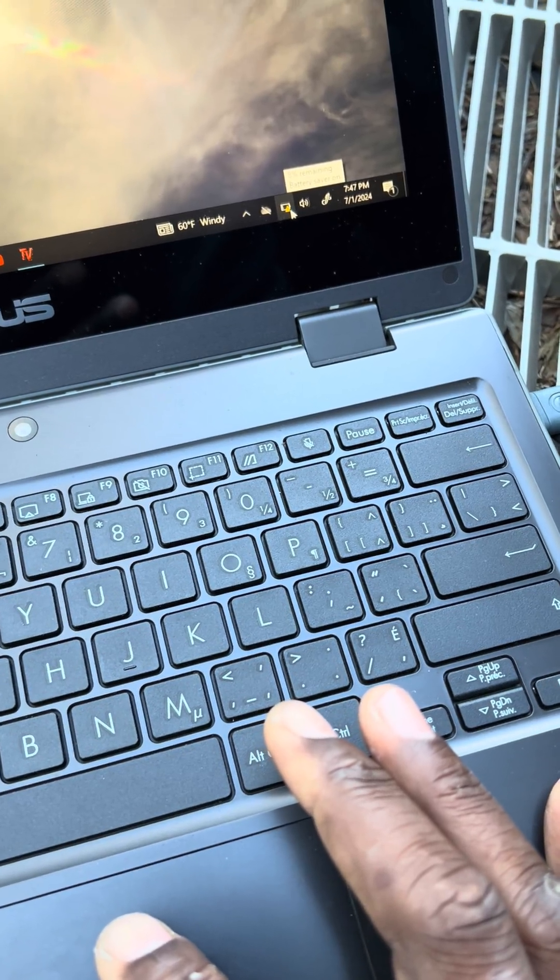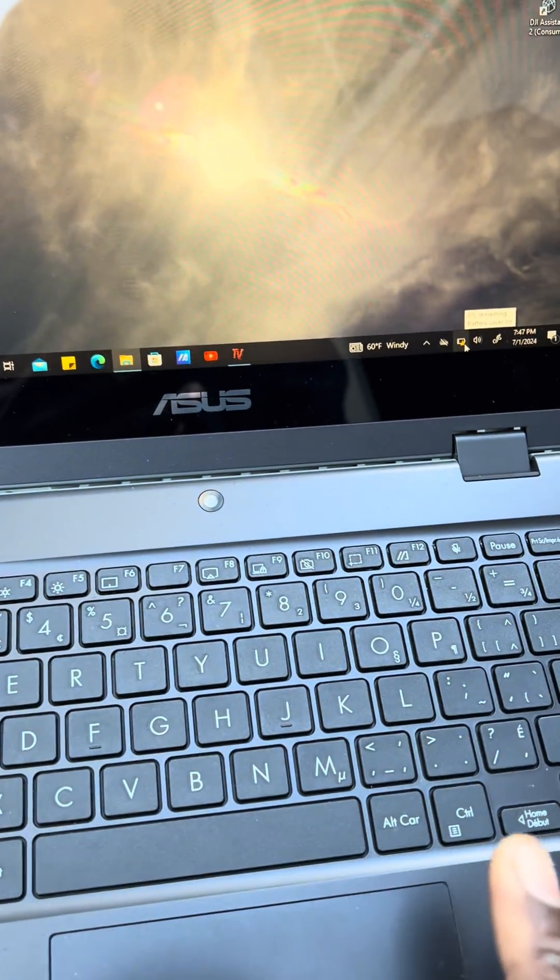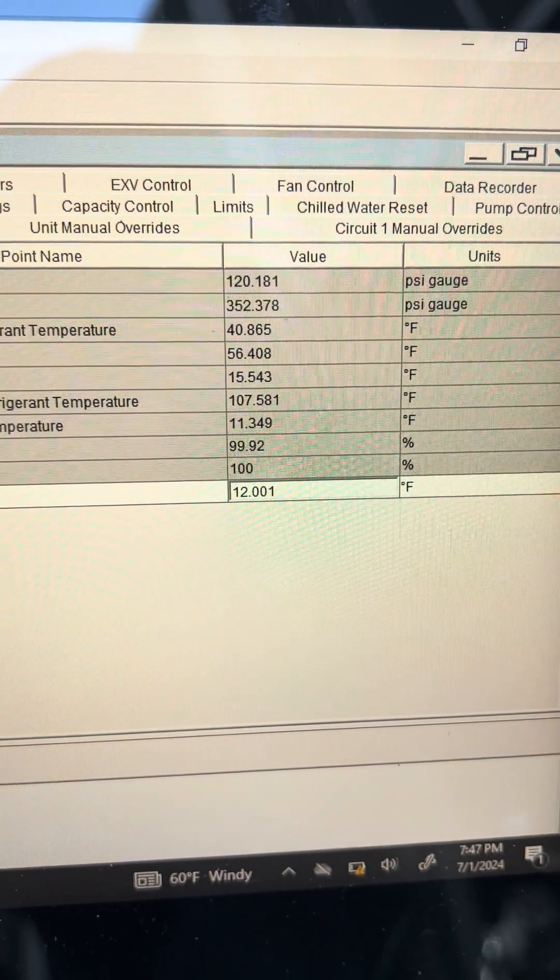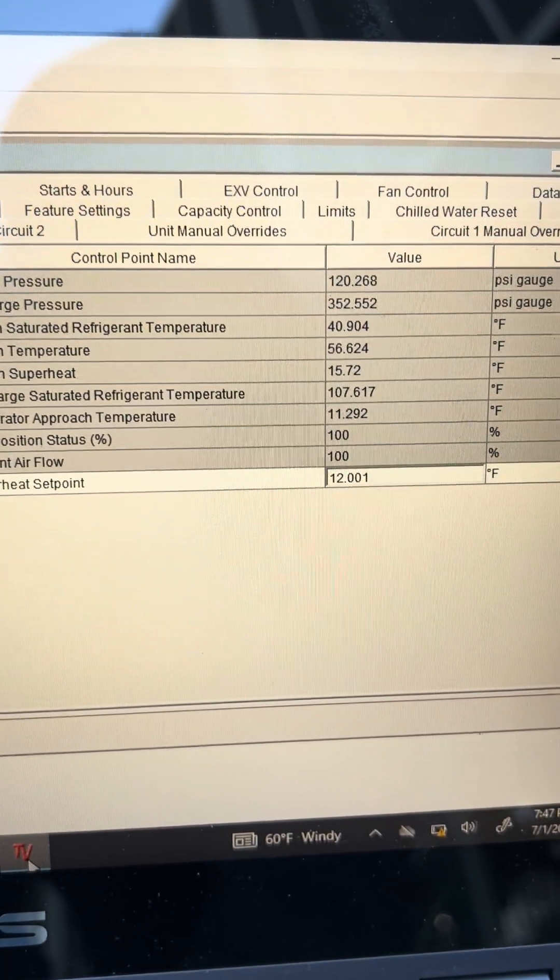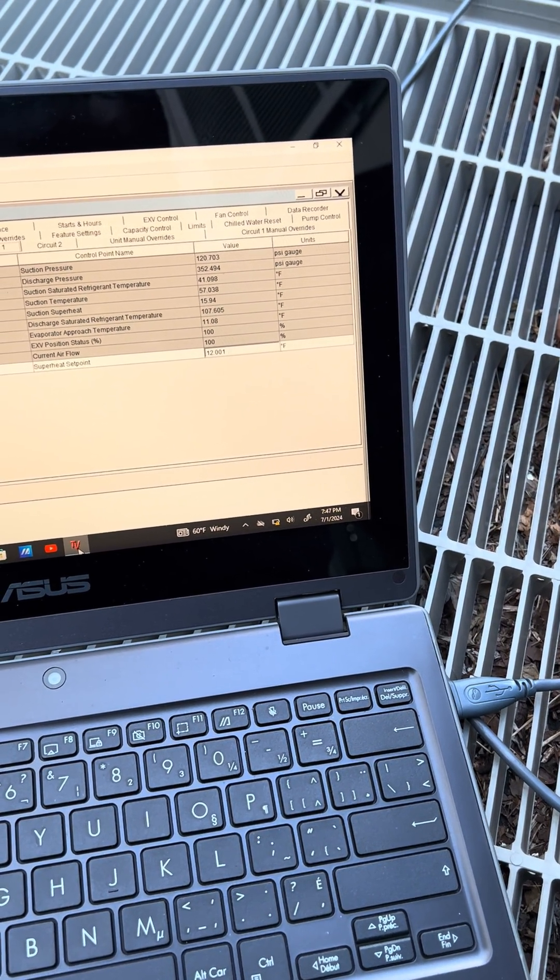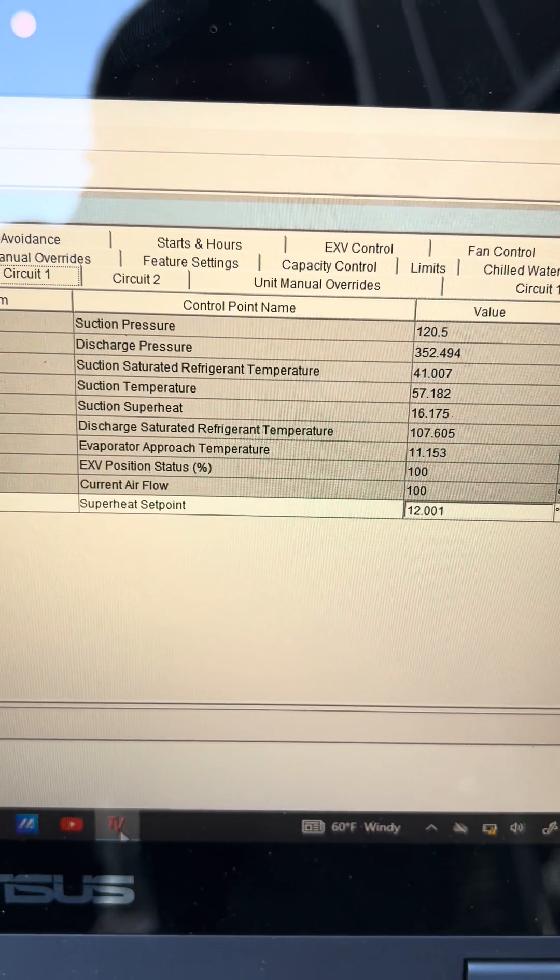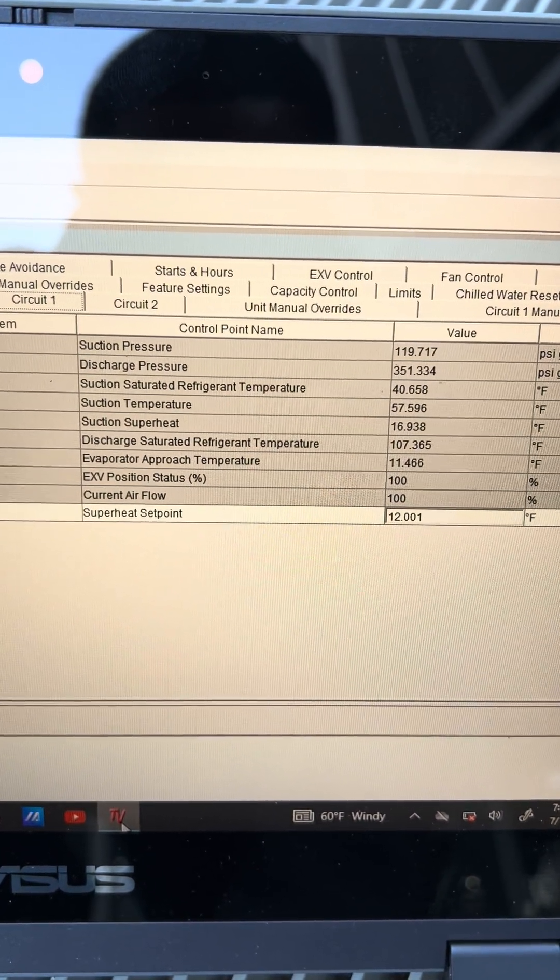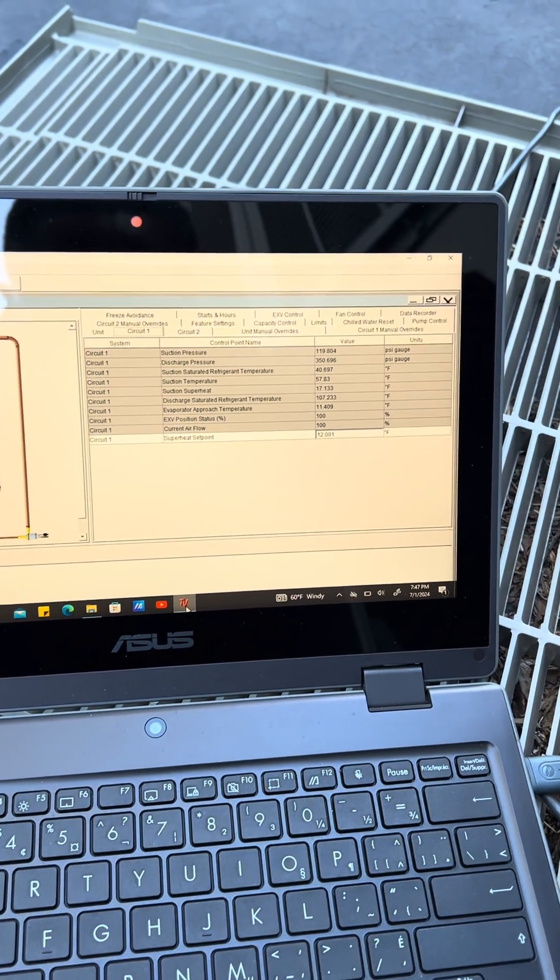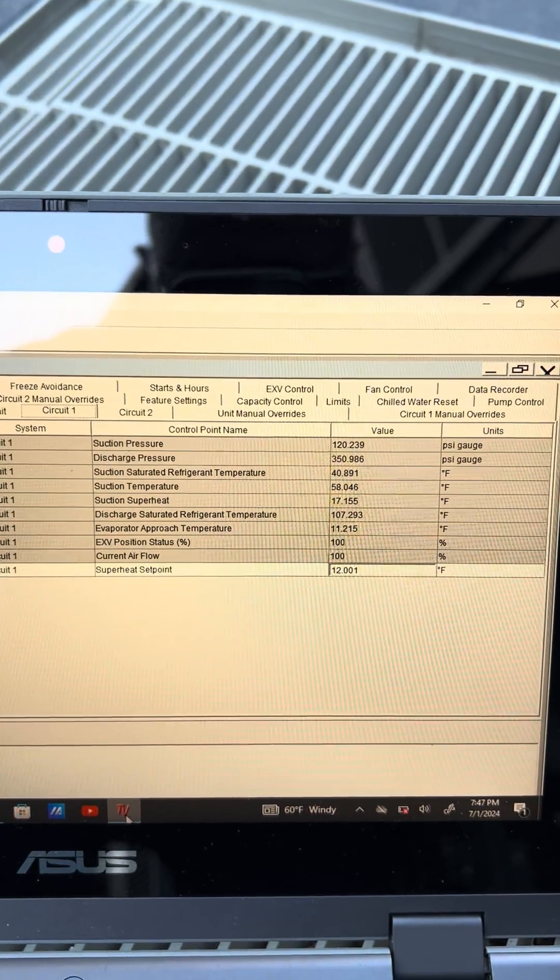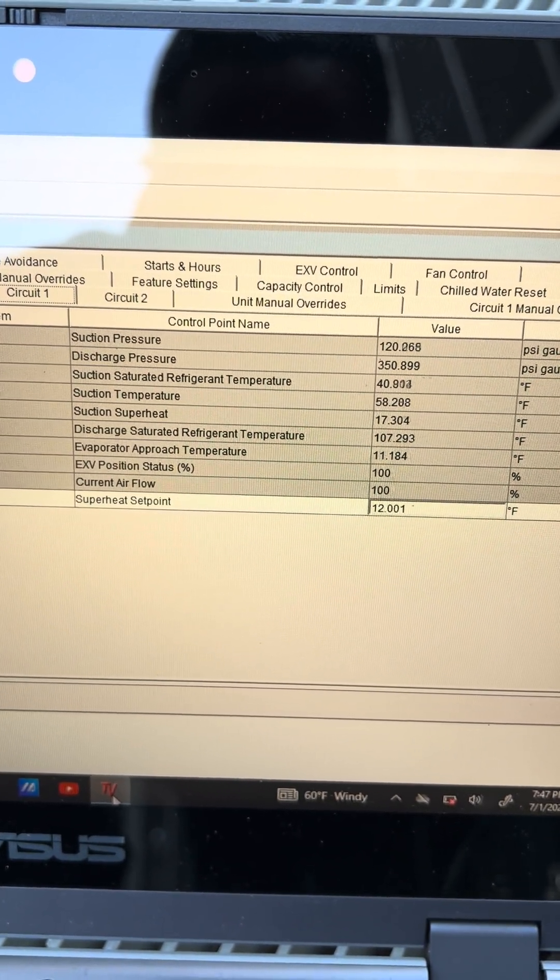All right, I have eight percent of battery remaining. I mean superheat is at 15 right now but we already know because we're passing the liquid over the sensor. That's why we have those numbers so low. Surprisingly my head pressure is not rising significantly with three pounds added but my back pressure is coming up though.